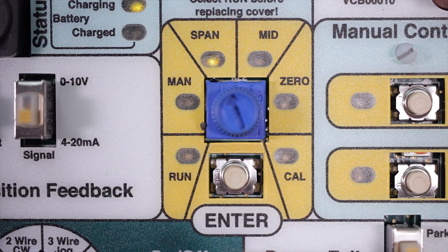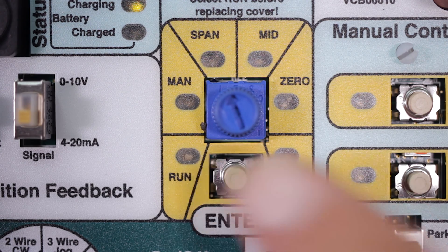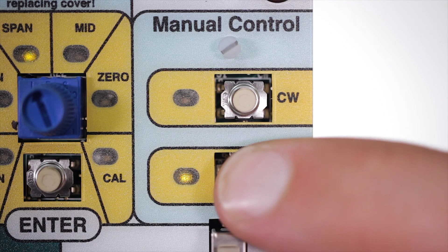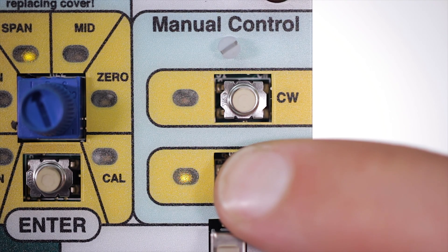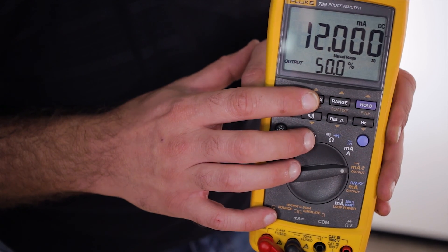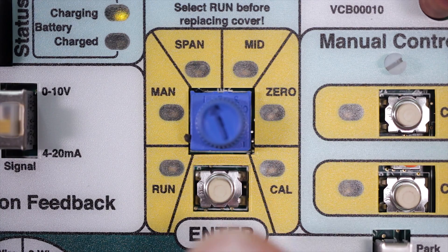Now move your operation mode selector switch to the span setting and hold down the enter button for two seconds until the LED is flashing. Use the counterclockwise button to manually drive the valve fully open. Send a 20 milliamp signal to the actuator from your loop calibrator. Then push the enter button.